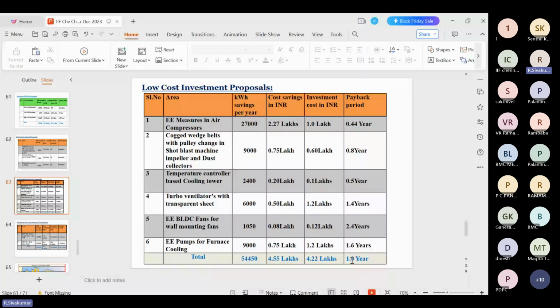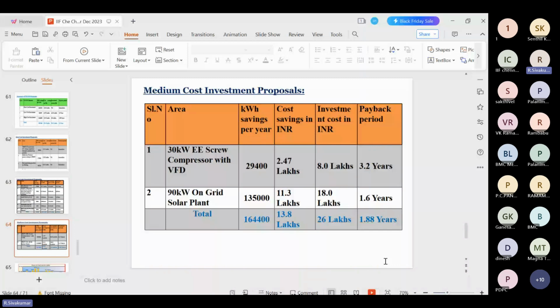For the medium cost investment, the compressor can be changed to a 30 kilowatt energy efficient compressor with VFD. 29,400 units can be saved. 8 lakhs is the investment, 2.47 lakhs is the saving, so 3.2 years is the payback period.